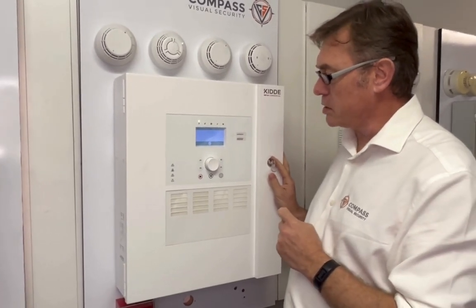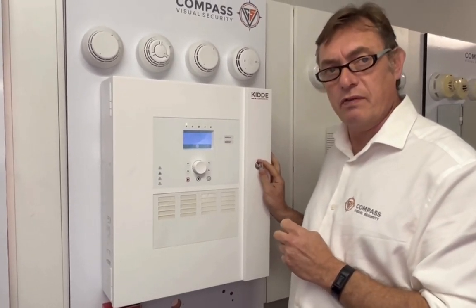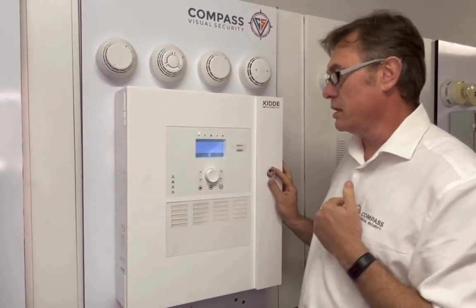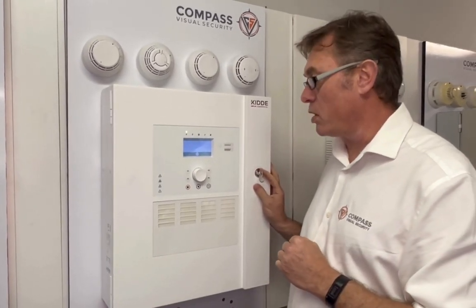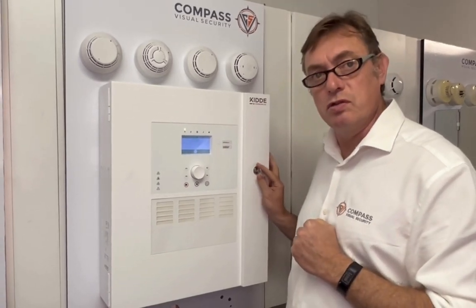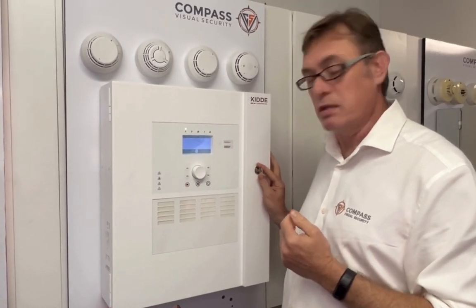In today's module we are looking at the Kidde Excellence Fire Panel: how to disable the device, how to silence the panel, and how to isolate problems on the loop. The commercial fire panel, I'm going to just show you how to disable a device. If we have a faulty device that keeps going to fault, maybe we need to get more parts, a replacement detector for instance, so we may need to disable the device in the meantime.